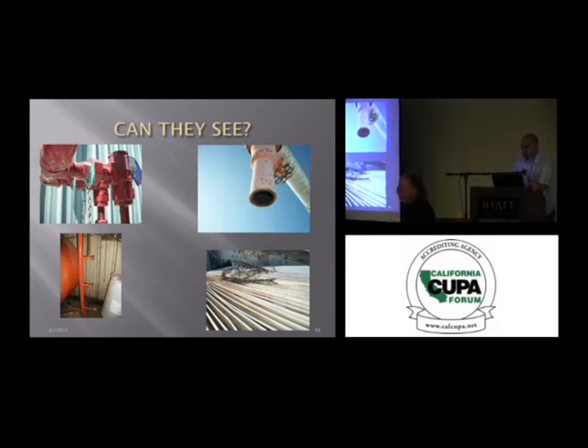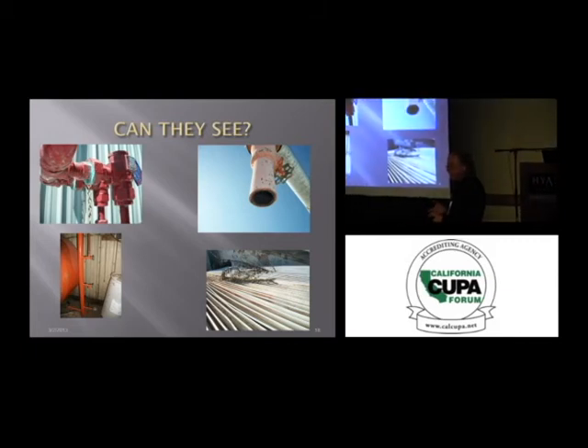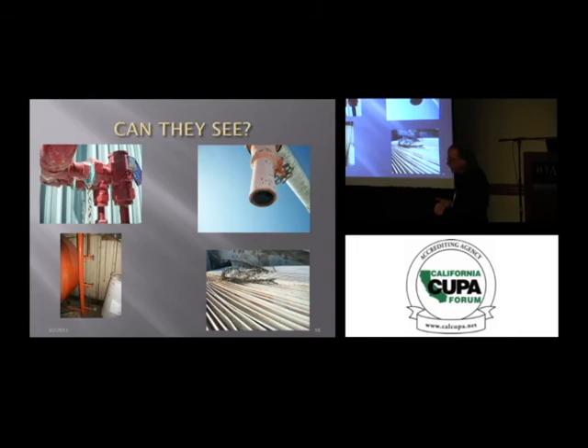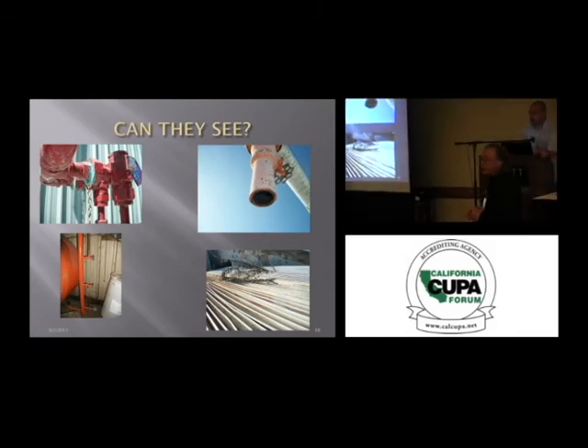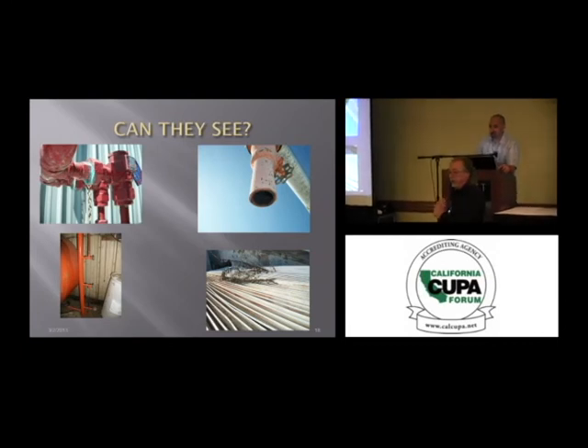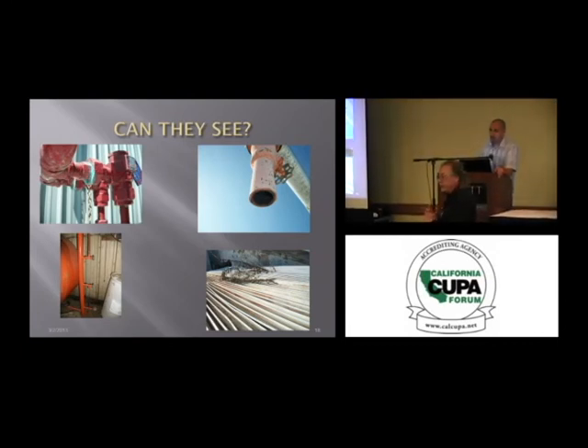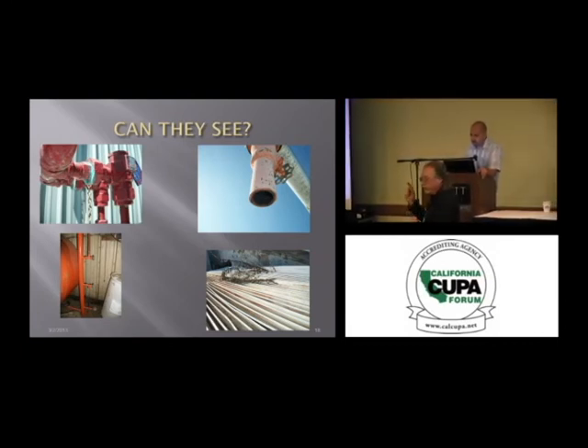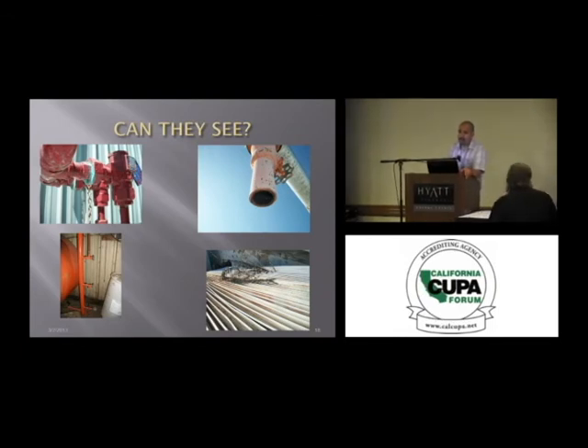We have a terrible problem in this industry with our water treatment people. They test the pH, the conductivity, they look at the bleed, they look at the cycles of concentration, etc. And they're the ones that are selling you the chemical to take care of your condensers, and they never go up there and inspect the condensers. A good water treatment guy will go up there. All the sites should be following their water treatment guys around to make sure they're actually inspecting the condensers to see what's going on. This particular condenser has been replaced.